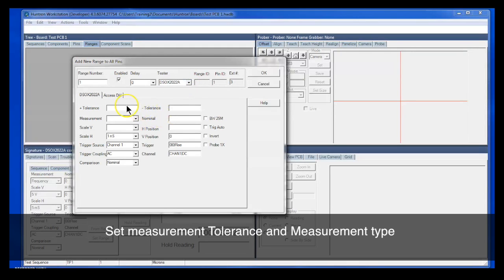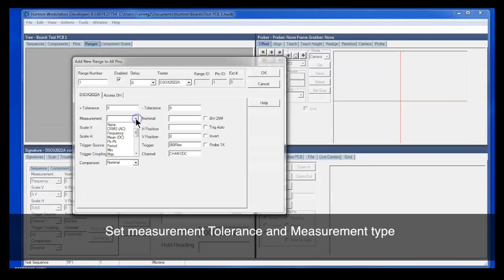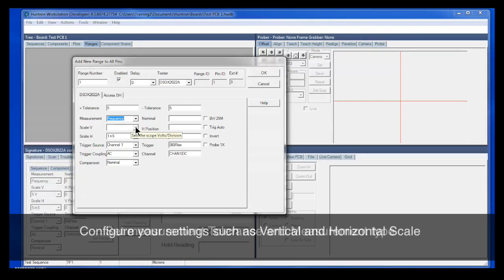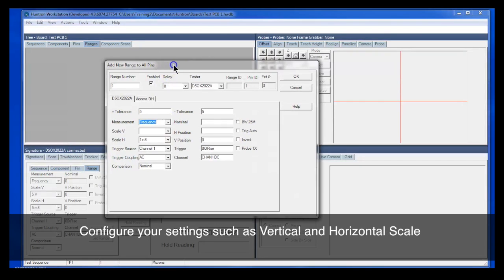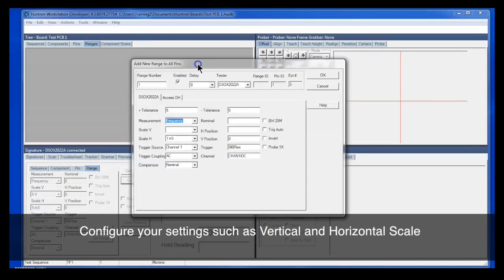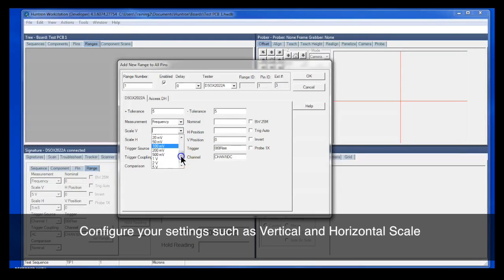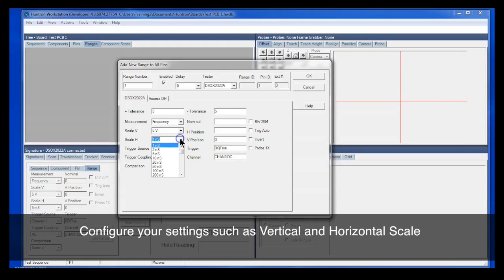So we'll select our tester type as our new test instrument, our oscilloscope. We're going to put in a tolerance. This will be a percentage tolerance. We're going to select our measurement as a frequency. And then again, we'll set our horizontal and vertical scales. I'm just going to base it on what I had set earlier. So I'll use what I can see in the range tab right now on this signature pane.